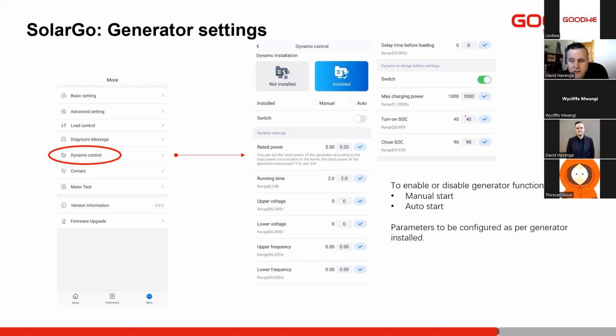The generator will start up, it will have the delay here, will then connect to the inverter. The inverter will start to charge the batteries. And then once the batteries reach 90% or 100% or 95%, switch off. So it will switch the generator off and then continue to work.